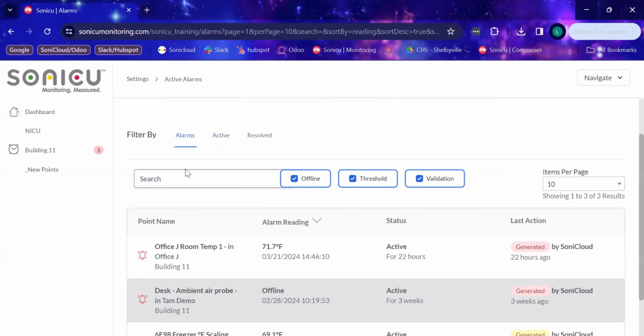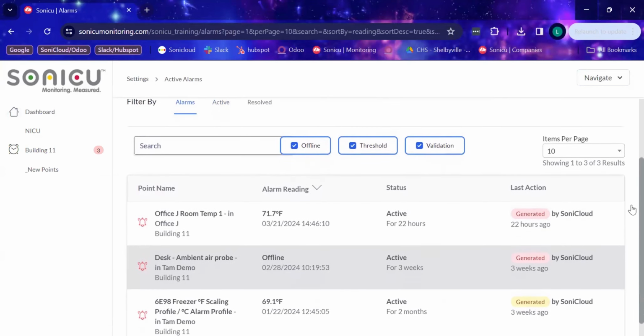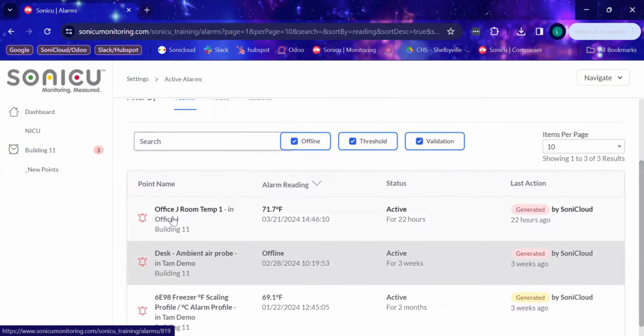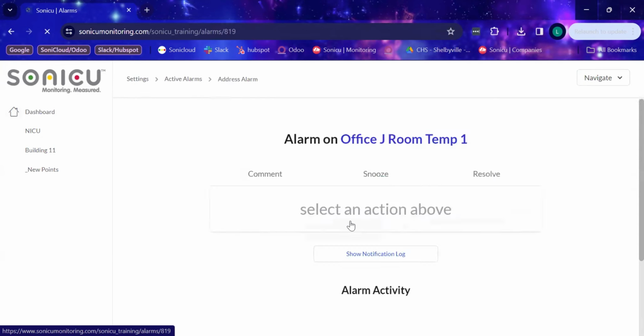We're going to go back to just alarms and look at this top one here. First it gives me the point name, so Office J Room Temp 1, in the Office J zone in the Building 11 area, here. It gives me the reading with the date and time, and the status — this one's been active for 22 hours, and the last action was generated by SoniCloud 22 hours ago. If I wanted to handle this alarm or take action on it, I can click into it.